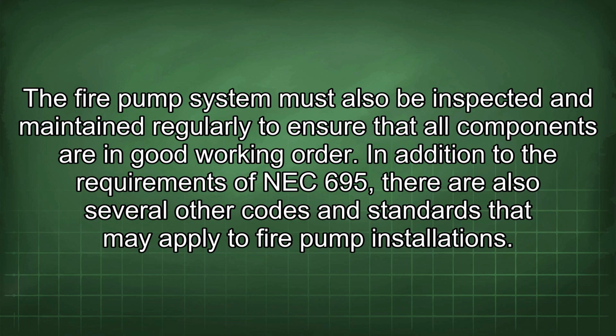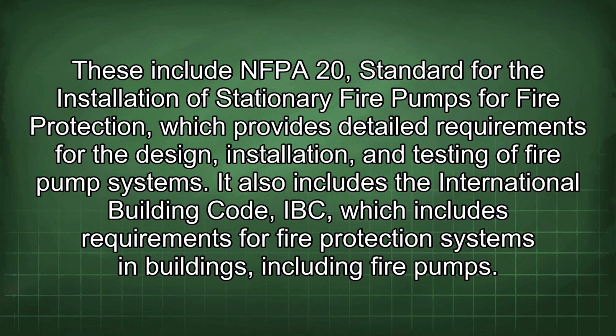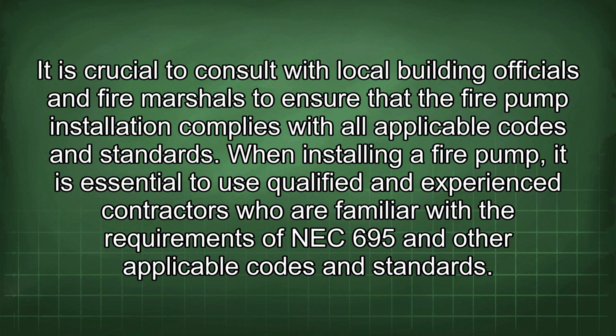In addition to the requirements of NEC 695, there are also several other codes and standards that may apply to fire pump installations. These include the NFPA 20 standard for the installation of stationary fire pumps for fire protection, which provides detailed requirements for the design, installation, and testing of fire pump systems. It also includes the International Building Code, IBC, which includes requirements for fire protection systems in buildings, including fire pumps. It is crucial to consult with local building officials and fire marshals to ensure that the fire pump installation complies with all applicable codes and standards.